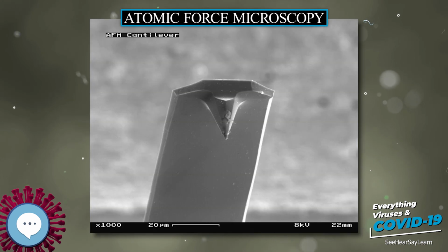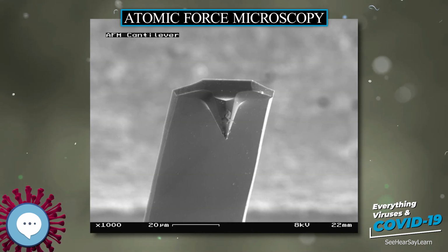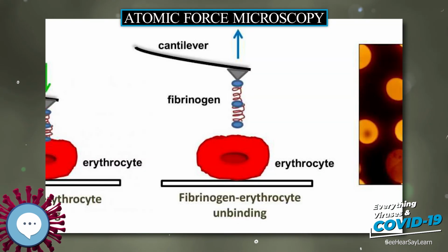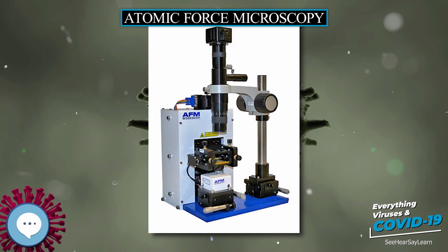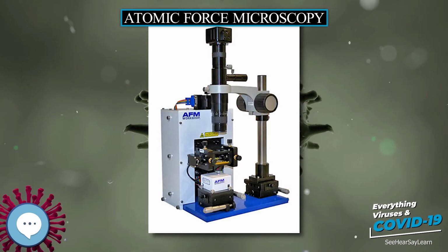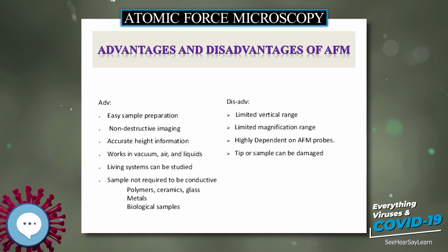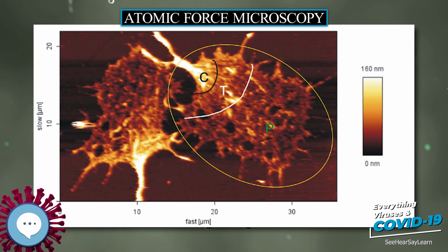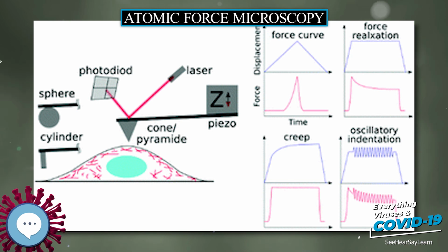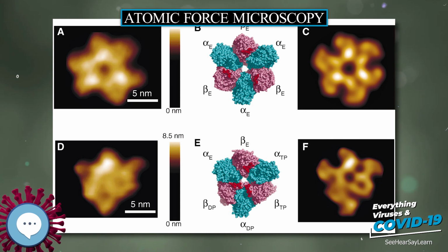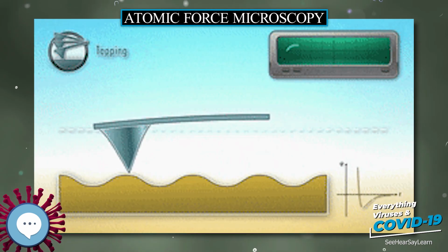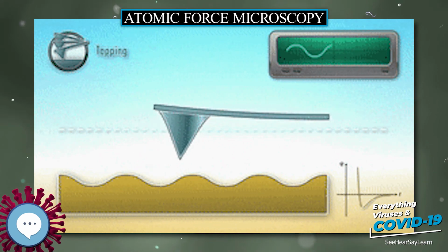Another popular design for AFM scanners is the flexure stage, which uses separate piezos for each axis and couples them through a flexure mechanism. Scanners are characterized by their sensitivity, which is the ratio of piezo movement to piezo voltage, that is, by how much the piezo material extends or contracts per applied volt. Because of differences in material or size, the sensitivity varies from scanner to scanner. Sensitivity varies nonlinearly with respect to scan size. Piezo scanners exhibit more sensitivity at the end than at the beginning of a scan. This causes the forward and reverse scans to behave differently and display hysteresis between the two scan directions.